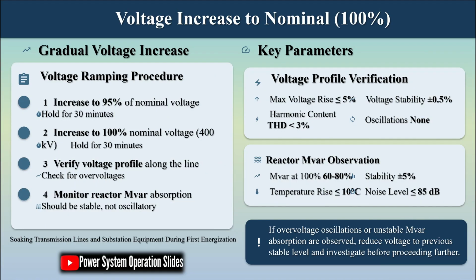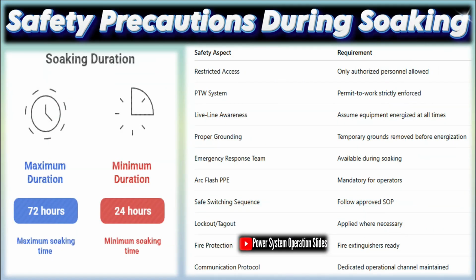By maintaining voltage on the equipment for an extended period, engineers can identify abnormal leakage currents, partial discharge activity, localized heating, or other indicators of insulation deterioration. Defects that may remain undetected during short-duration tests often become evident during prolonged soaking because insulation weaknesses tend to manifest when exposed to continuous electrical stress.